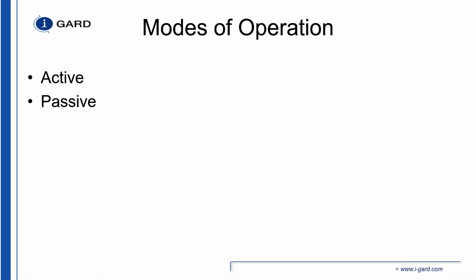The difference between the two is that active monitoring of the neutral grounding resistor means that when the system is de-energized and there's no voltage on the transformer, as long as we have control power, we can actively monitor the integrity of that resistor and that path by injecting a signal onto the neutral and resistor through the NGRS and NGRX system that we have. Passive is we basically measure the voltage and measure the current that's on the system and determine whether the resistor is within tolerance or not.